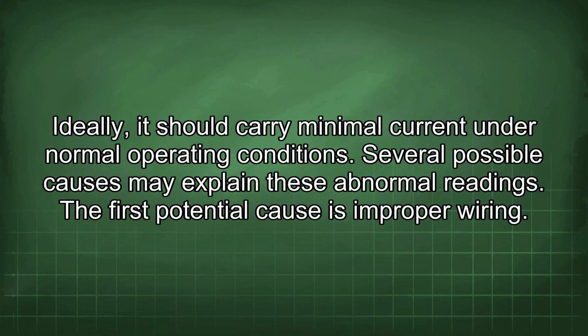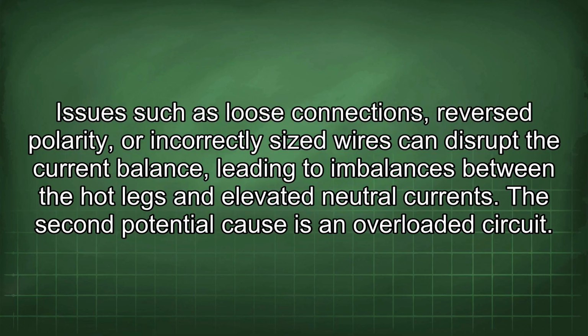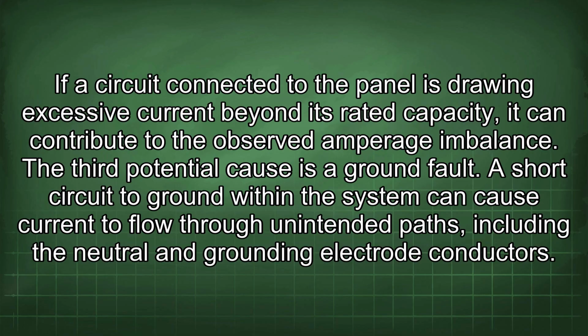The first potential cause is improper wiring. Issues such as loose connections, reversed polarity, or incorrectly sized wires can disrupt the current balance, leading to imbalances between the hot legs and elevated neutral currents. The second potential cause is an overloaded circuit. If a circuit connected to the panel is drawing excessive current beyond its rated capacity, it can contribute to the observed amperage imbalance. The third potential cause is a ground fault.